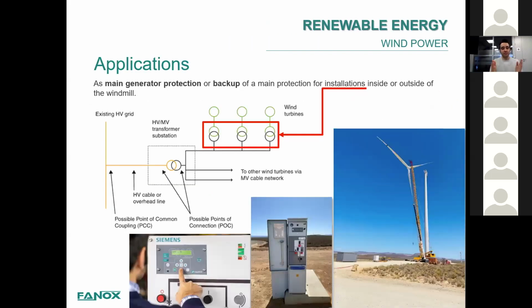Okay, so now we are going to start with wind power energy. Our relays have been installed and are working as main protection for the generator, or also as a backup for the bigger or more complex relay that is providing the first step of protection of the generator. But the self-power relay acts as a backup. It can be inside or outside the windmill.